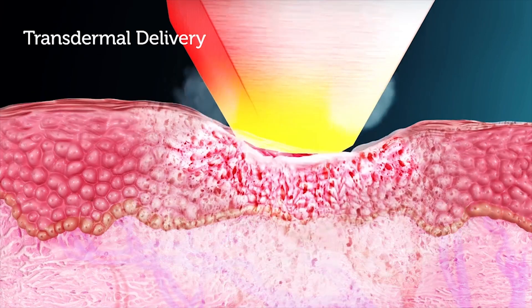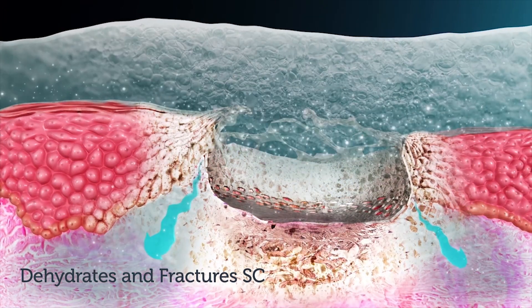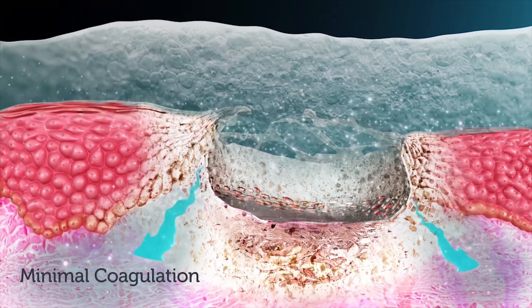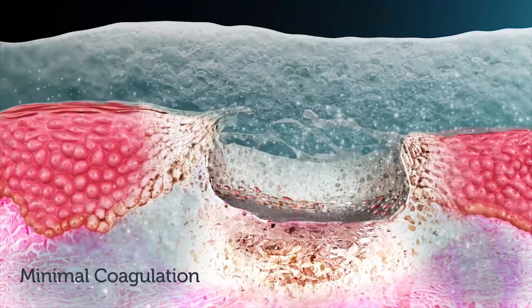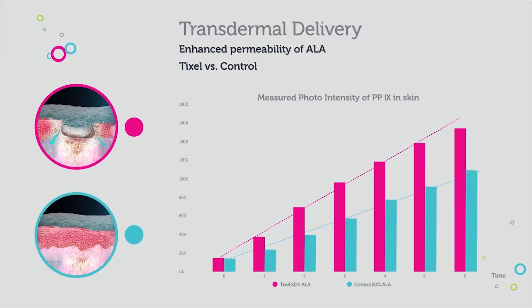Tixel can also be used for transdermal delivery. The tip dehydrates and fractures the stratum corneum upon contact with minimal underlying coagulation. The result is a long-lasting open channel, exhibiting enhanced absorption and diffusion into the skin. An in vivo study shows 40% greater permeability of 20% ALA with Tixel versus control.